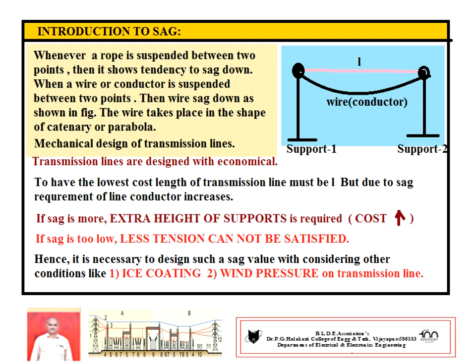Before going to the calculation of sag, some important points we have to remember. When the supports are equal, that means the height of A and the height of B are both equal, then the shape of the conductor is called the catenary curve. Second point, if the sag is small as compared to the span, that is the distance between supports A and B, then the sag span curve is a parabola. It takes the shape of a parabola as shown in the figure.